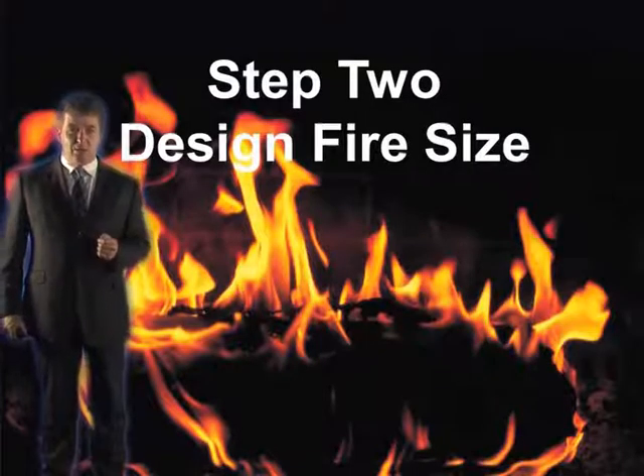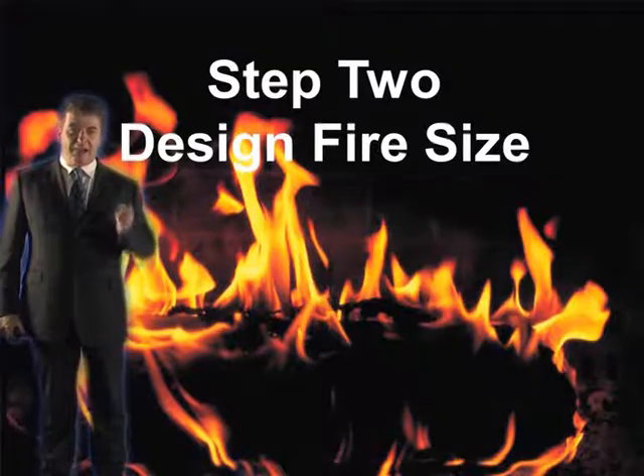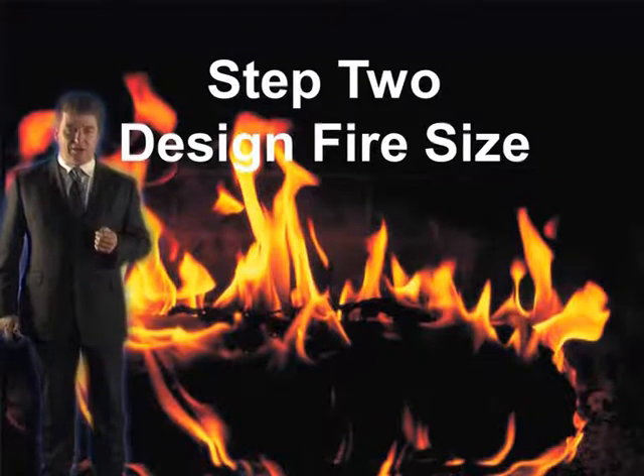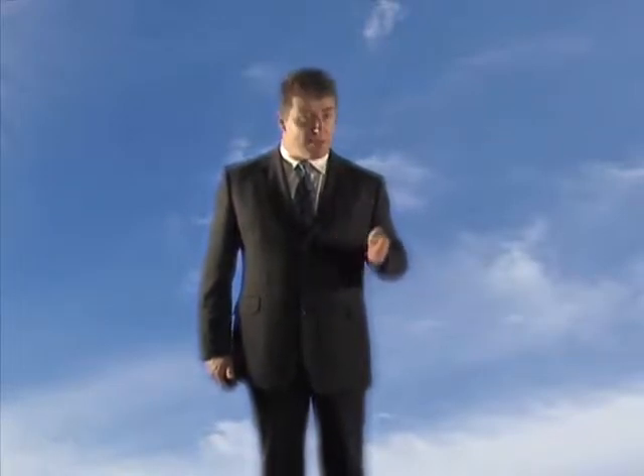Let's look at step 2. We need to determine the design fire size that's going to be adopted in the scheme. Now we have to establish a design fire size. Now we've done this from table 3.3 in BR368. You can see that a fire in a sprinklered office may grow to cover 16 square metres, with a perimeter of 14 metres and a convective heat output of 2,700 kilowatts. So that's from table 3.3 in BR368. That's where we got this data from.